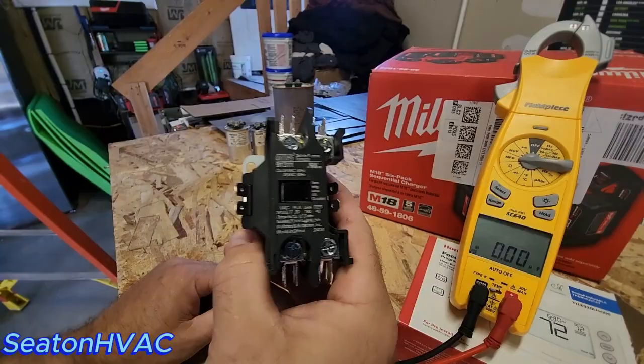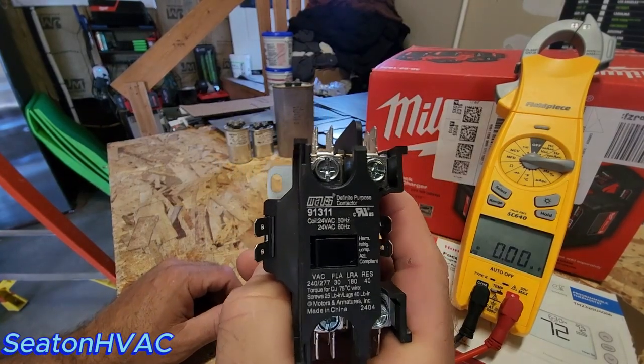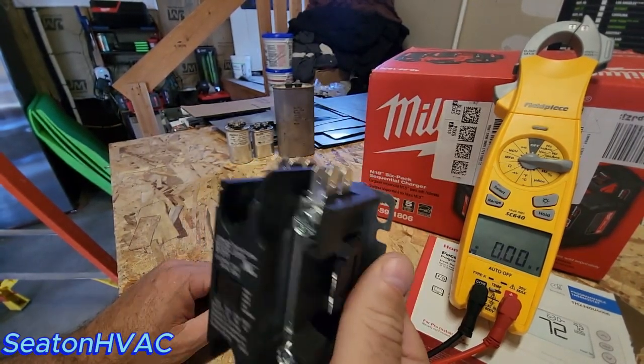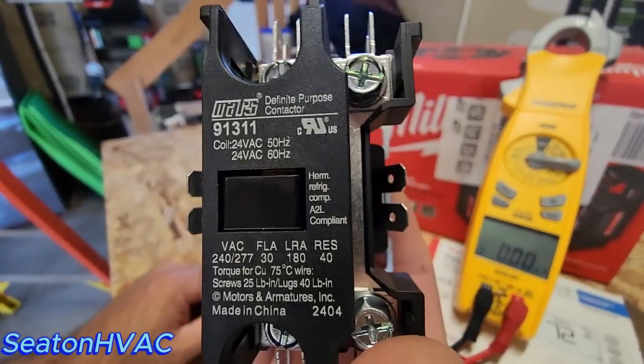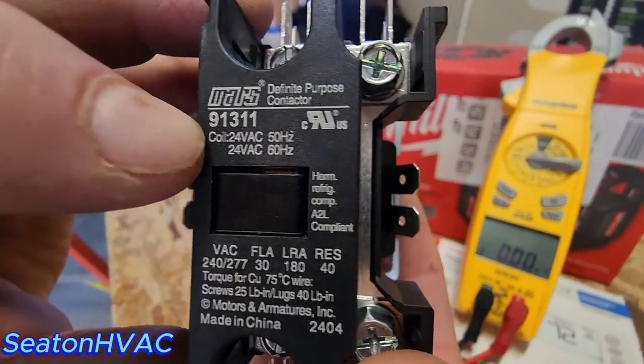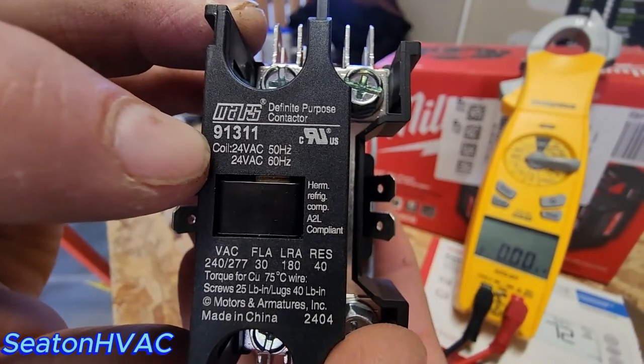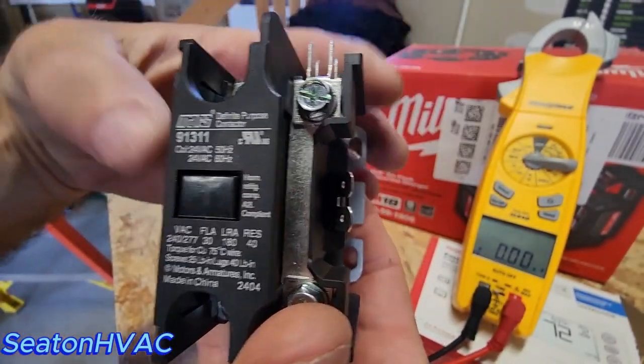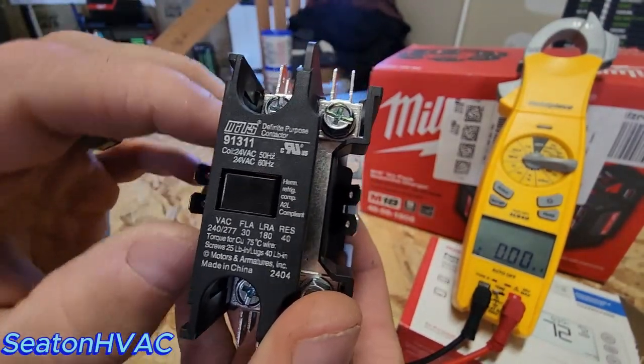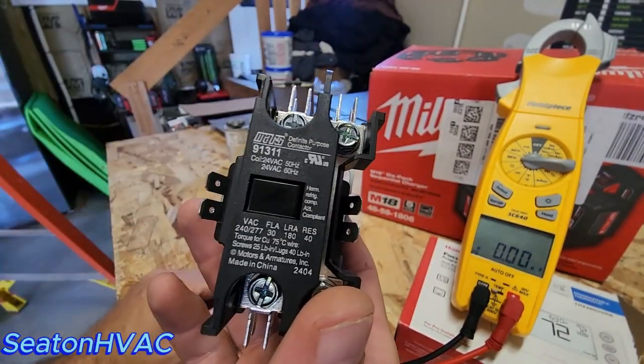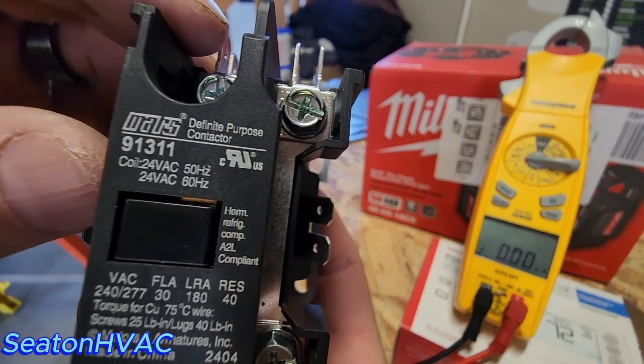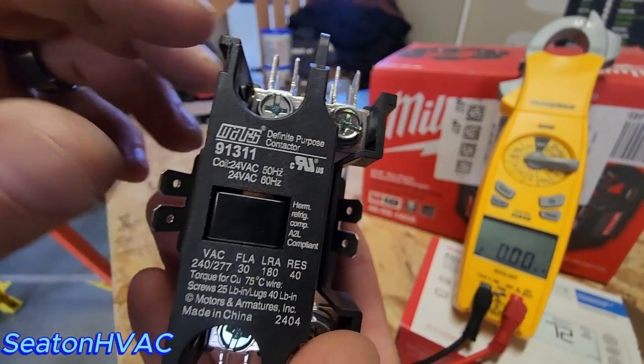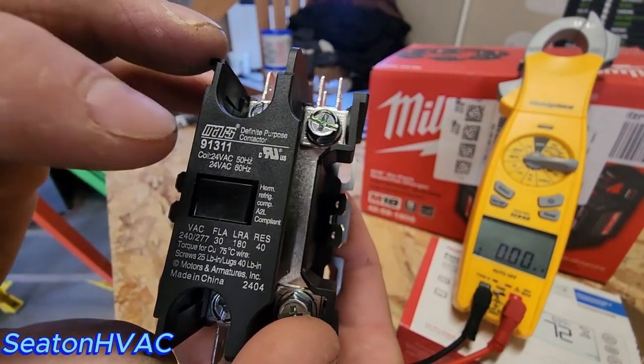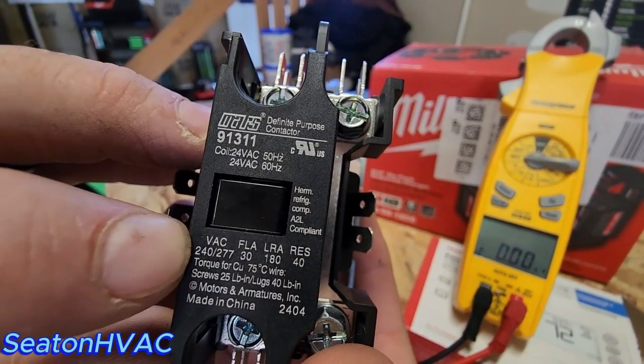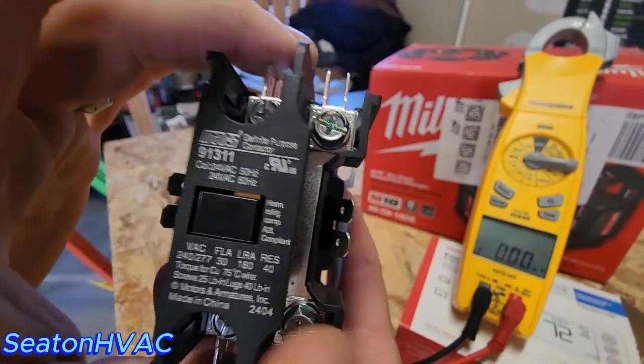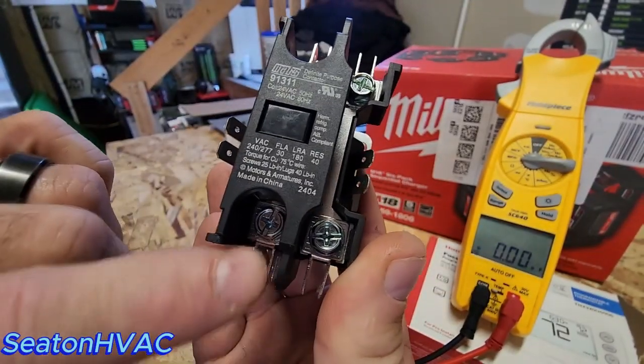All right, I got set up a little bit better here. So next on our list is our compressor contactor, or we can just call it a contactor. So what do these numbers on here mean? Okay, so we have our coil loads, right? It's a 24 volt VAC, volts AC, coil, which is back here. It's inside the shell. That's your resistance, that's your contactor coil. And then you have your hertz rating on it: 50 hertz, 60 hertz, general stuff there. And then on here we have our VAC, volts AC, 240 volts, and that's what this is here on the bottom. This is what these numbers are for.